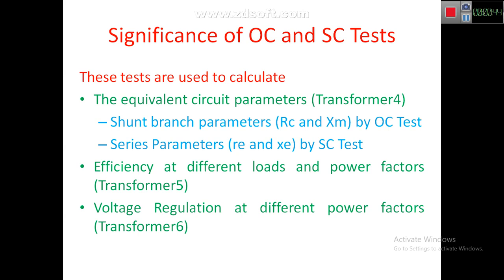These tests are used to calculate equivalent circuit parameters. We have already discussed the equivalent circuit of the transformer, where we have many parameters. The shunt branch parameters RC and XM can be calculated by using the OC test, and the series parameters RE and XE can be calculated by the short circuit test.